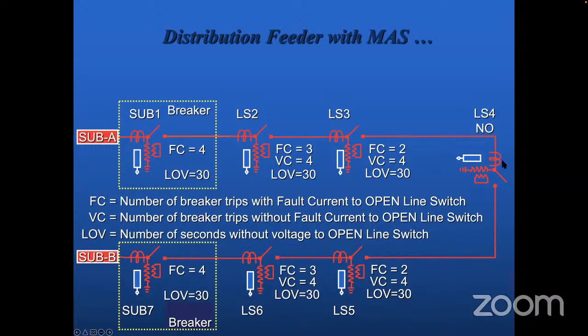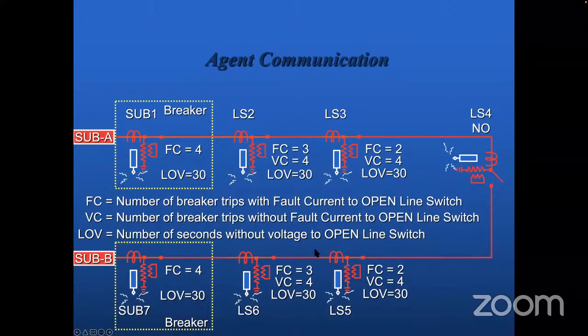LS4 is the normally open switch. Similarly for this side as well, with a 30-second setting and a fault count. Now all the switches are closed, supplying the load. So this is normal operation. This is two substations, two feeders, both having one tie switch, and at a couple of kilometers or miles you have radio communication.